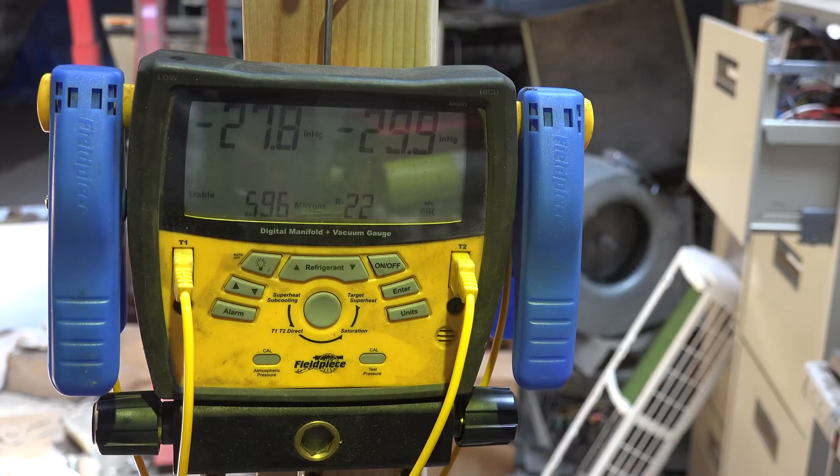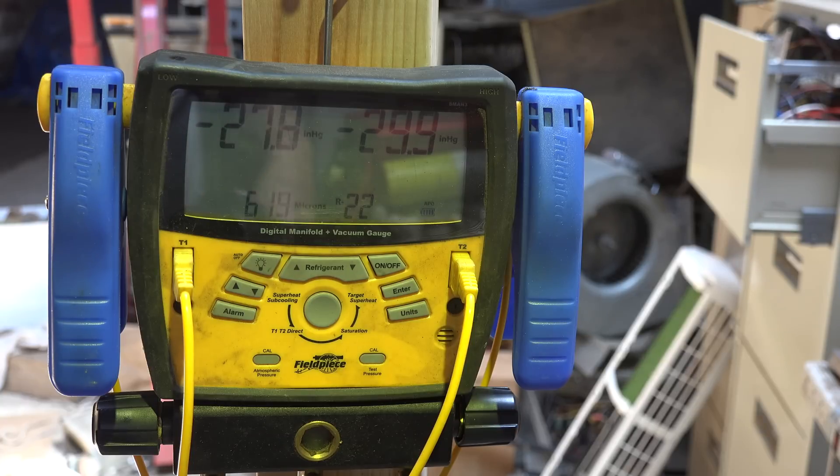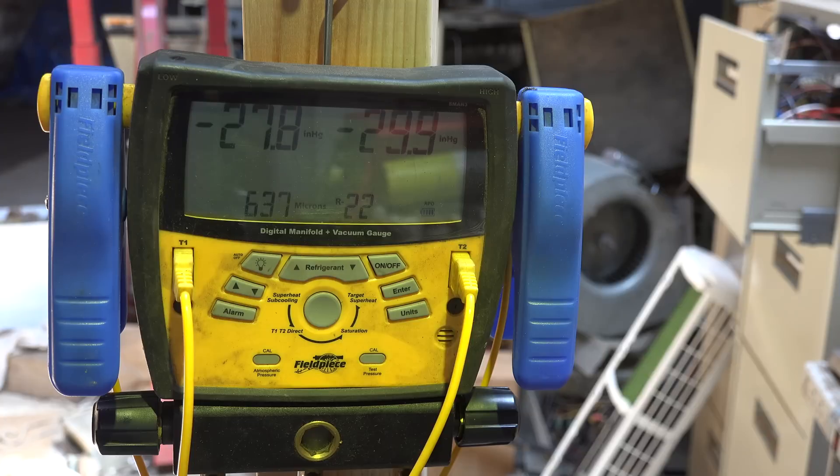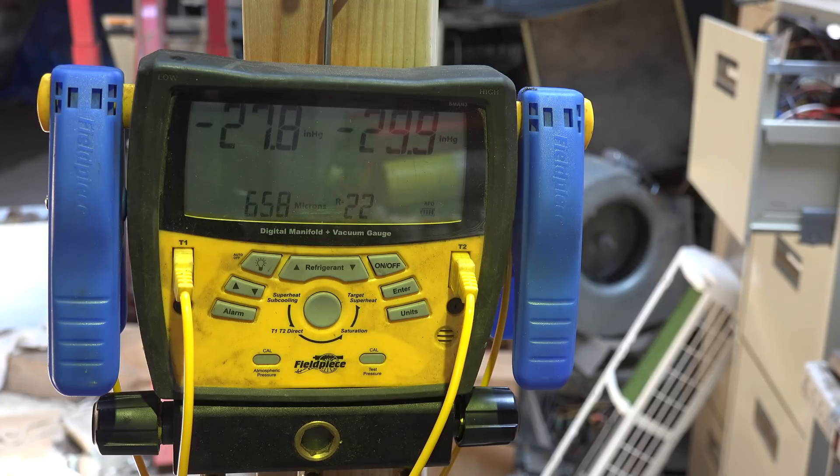I've started the stopwatch. While I'm waiting for this to happen, what we should see is it should go up somewhere between 1000 and 1500 microns and stay there.